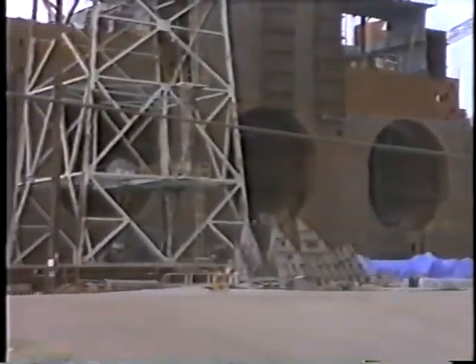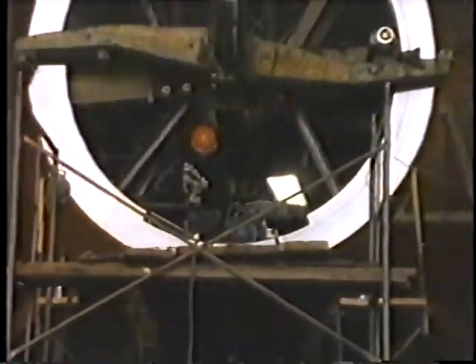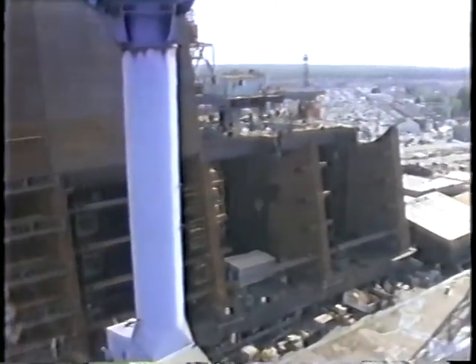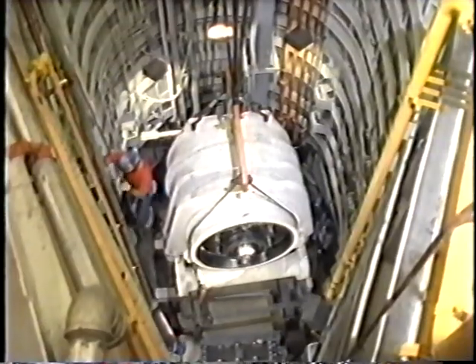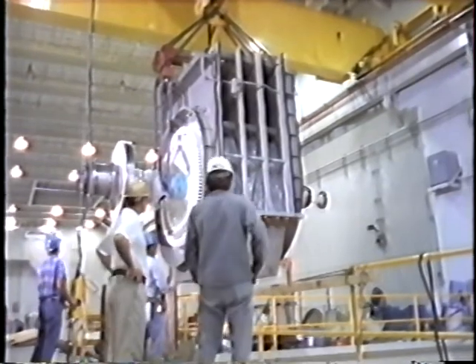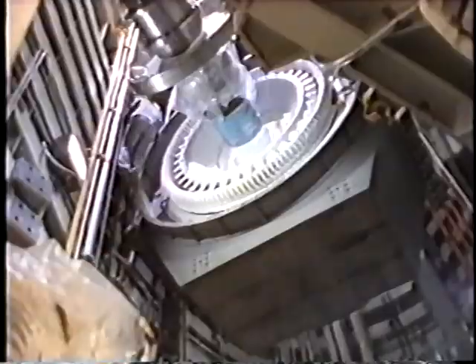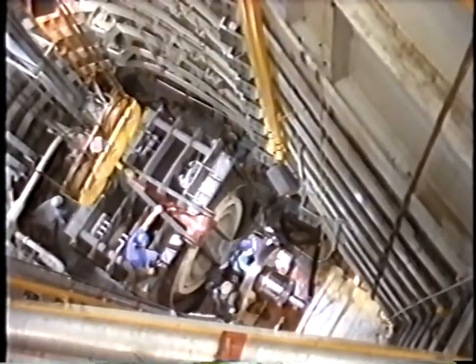The power plant houses 8 bulb-type turbines 323 inches in diameter, compared with 3 240-inch diameter turbines at Greenup. The 8 turbines provide a generating capacity of 192 megawatts, making it one of the largest low-head hydroelectric plants in the world. A further innovation was the speed increaser connecting the low-speed turbine to the generator, permitting the use of a less expensive generator. The power plant was built in 50 to 100-ton modules, each with its equipment in place.